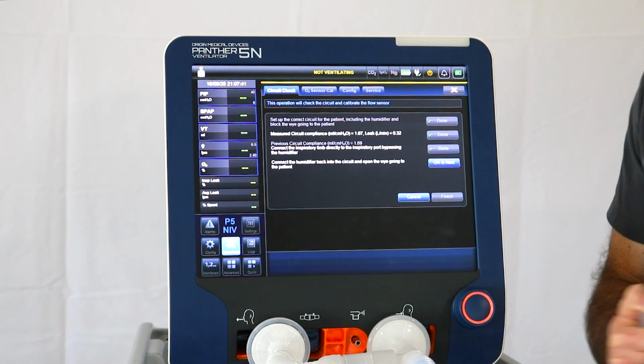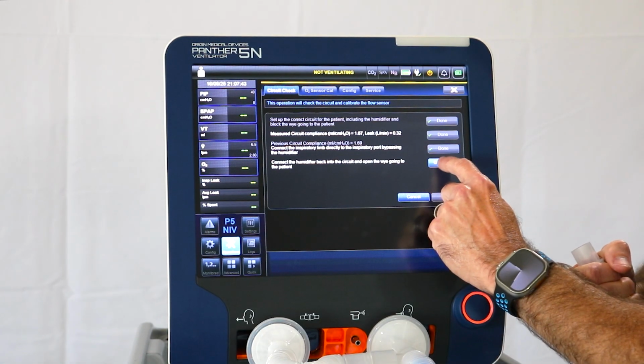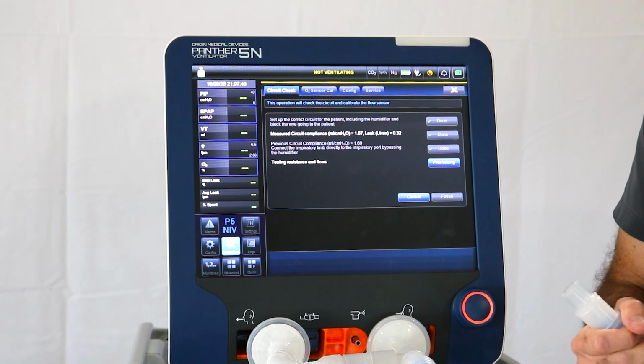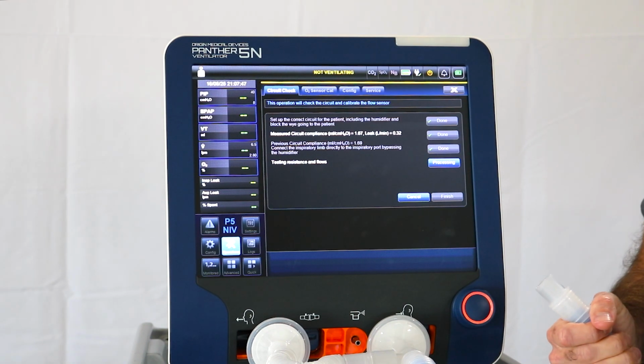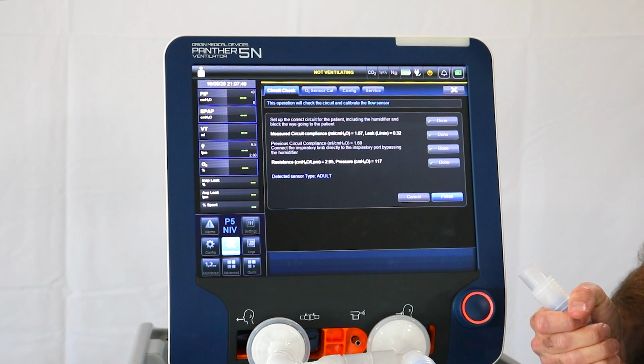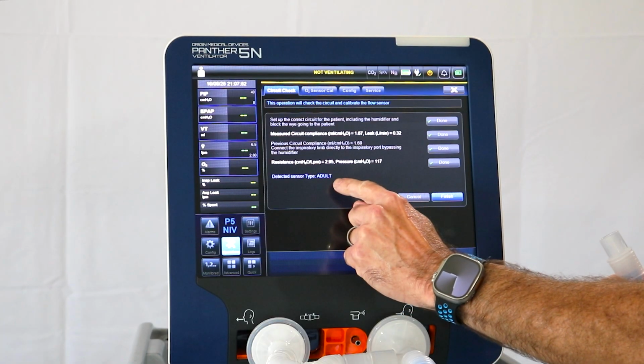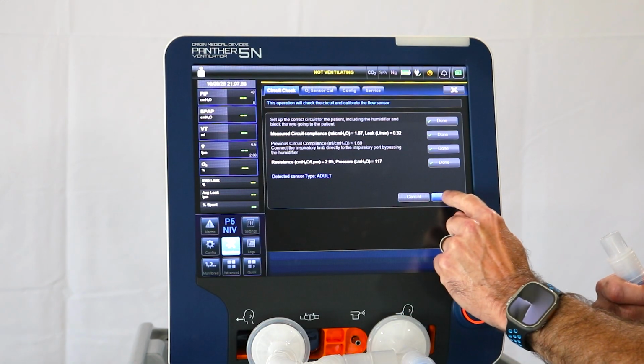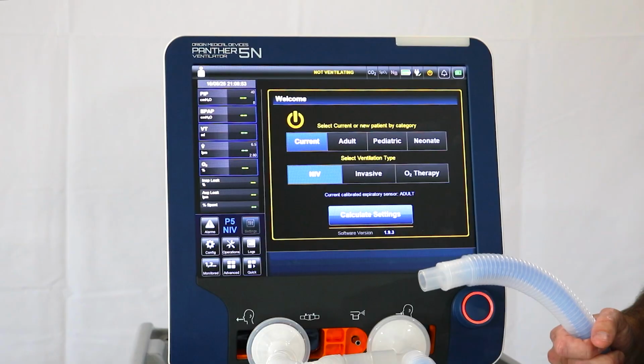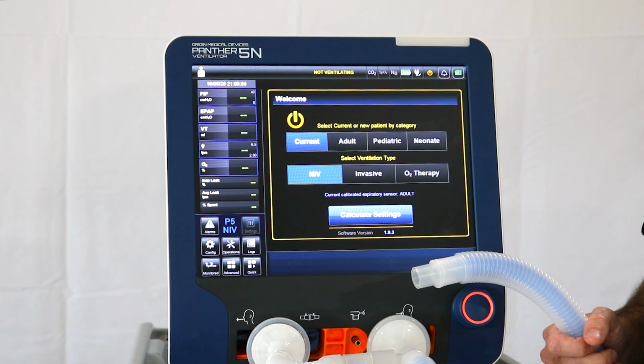For the final test, open the circuit to room air. An adult flow sensor has been detected. Press Finish. The circuit and expiratory flow sensor are now calibrated for patient use.